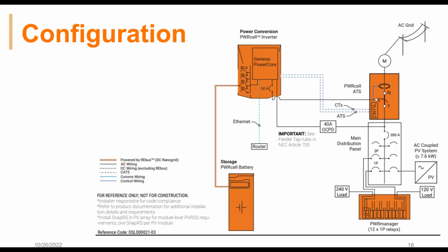Something else I should mention, folks, is that you can use the power manager to manage, again, up to 6 240 volt loads. You can use Generac's smart management modules to individually lock out any additional loads. The reality is, from what we've seen, most homes don't have more than 6 2-pole breakers in the main panel. Now that could be changing as homes are becoming more and more electrified with electric heat pumps for heat and AC, EV chargers, etc. In that case, if you have like 8 240 volt loads and you want to manage 4 of them, then I'd manage 4 of them through the power manager, lock out 2 in the power manager, and then use 2 of Generac's smart management modules to lock out the rest.